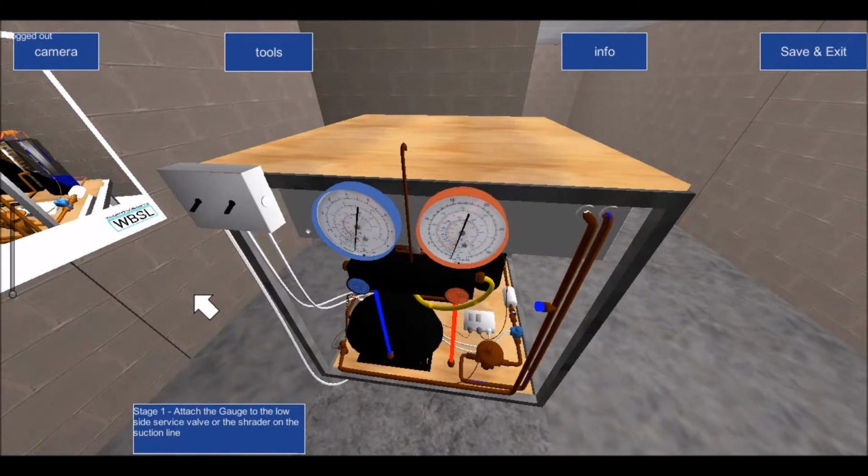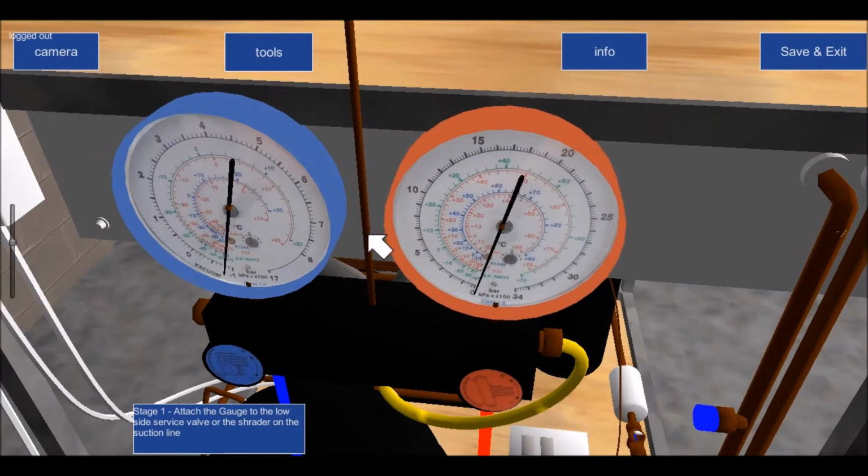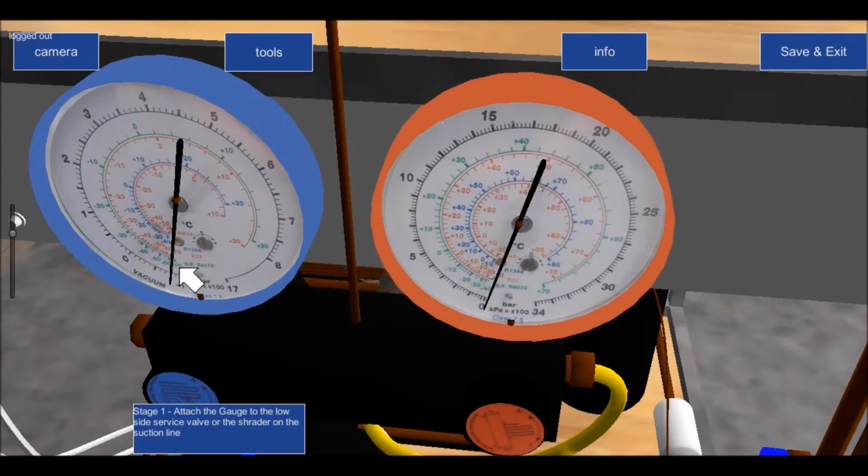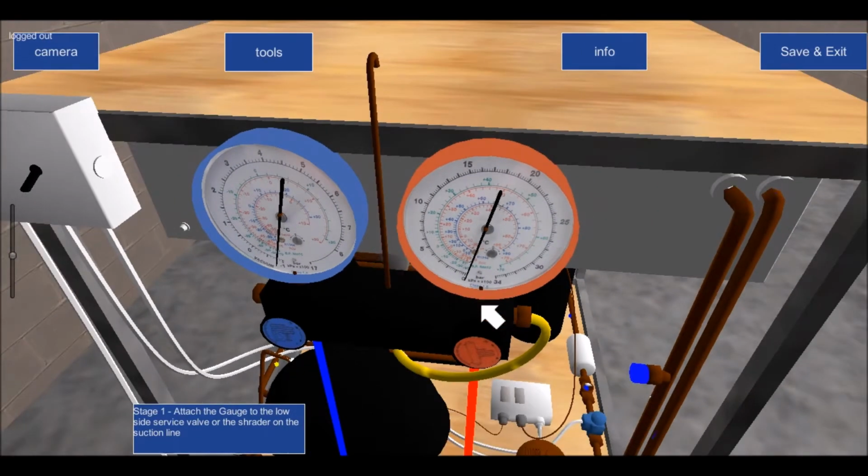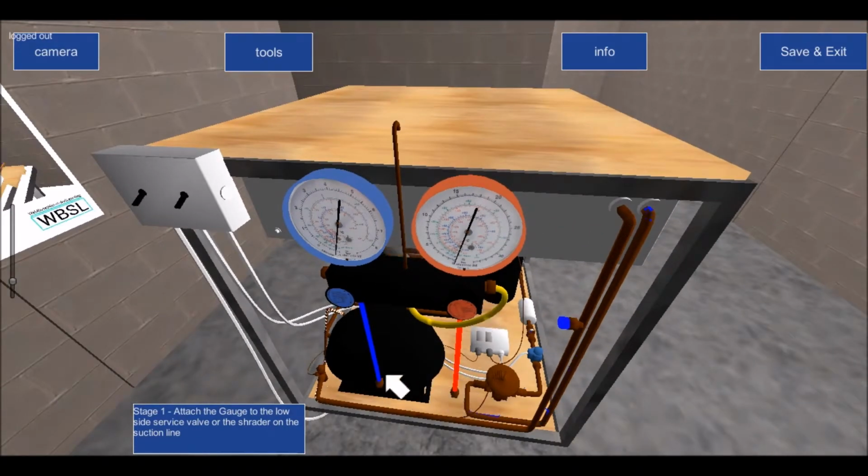Atmospheric pressure, as you've seen from an earlier slide, and probably Brendan covered in detail last week, is 1 bar. If we look at our gauges here, this one hasn't been sorted out, so just ignore it for the moment. I'll get on to Shane about that again. But our gauge is registering 0 bar. In other words, gauge pressure is 1 bar less than atmospheric pressure. This gauge is reading 0 bar, but the hoses are exposed to the air, so these hoses have air in them, because there's nothing to stop air entering them.